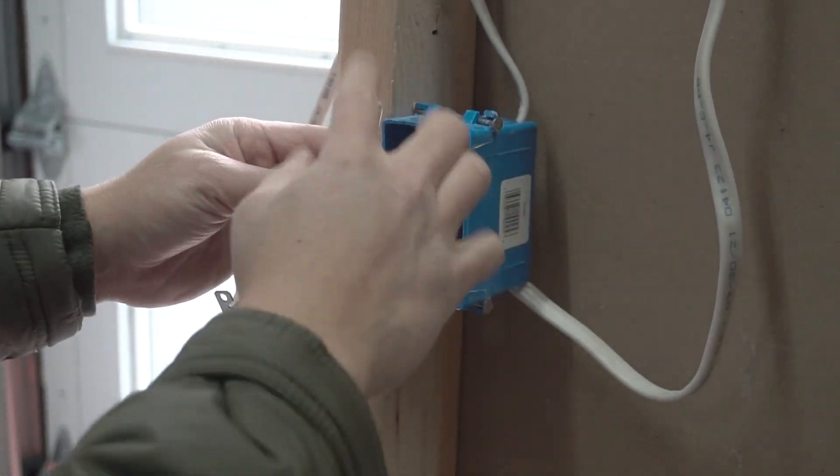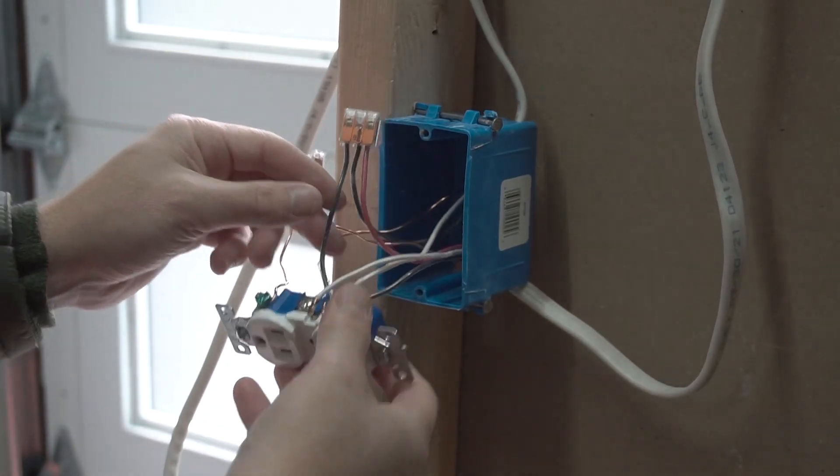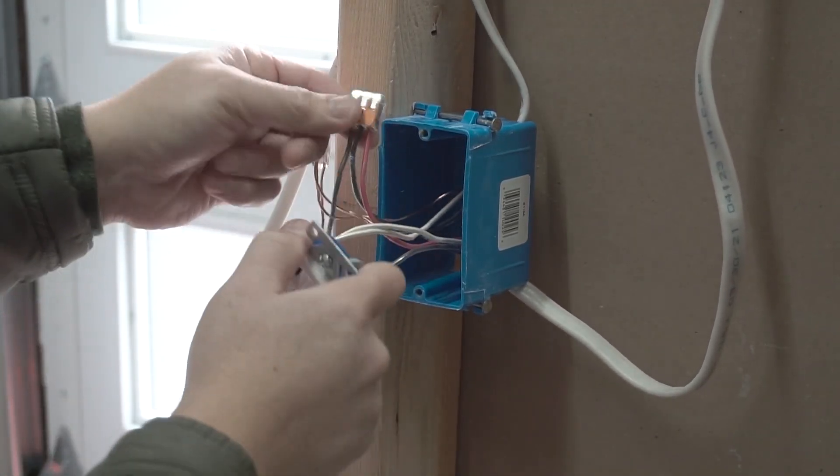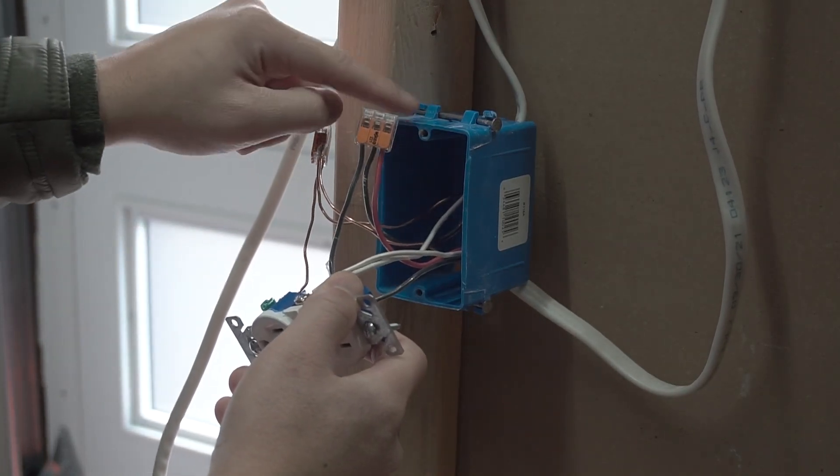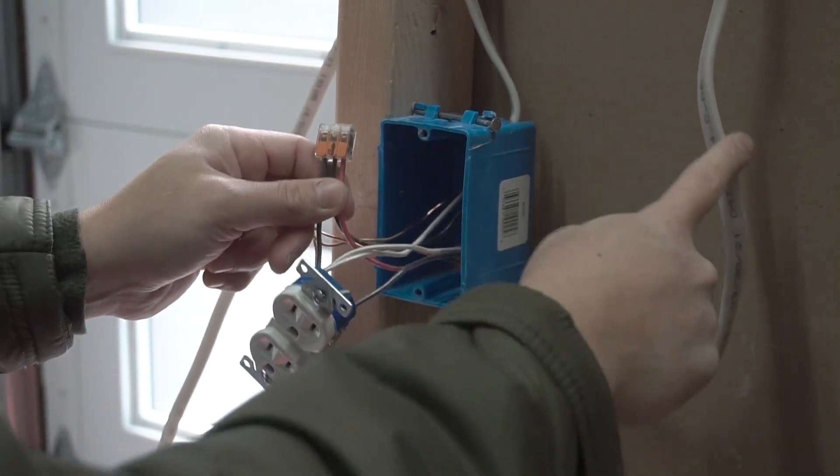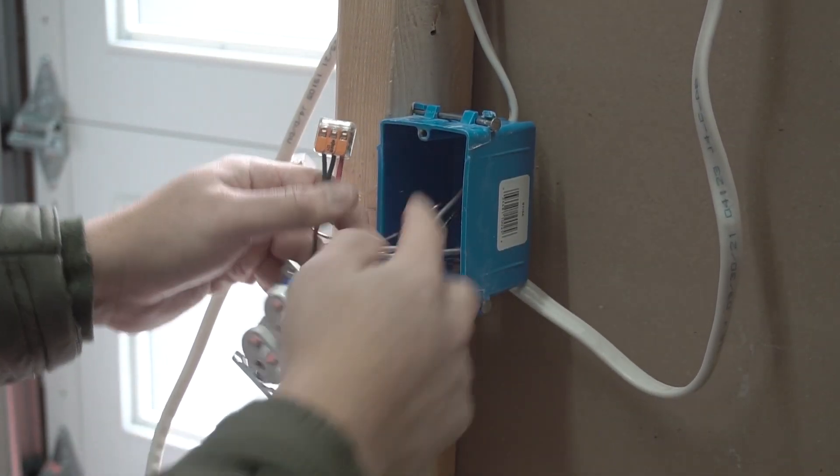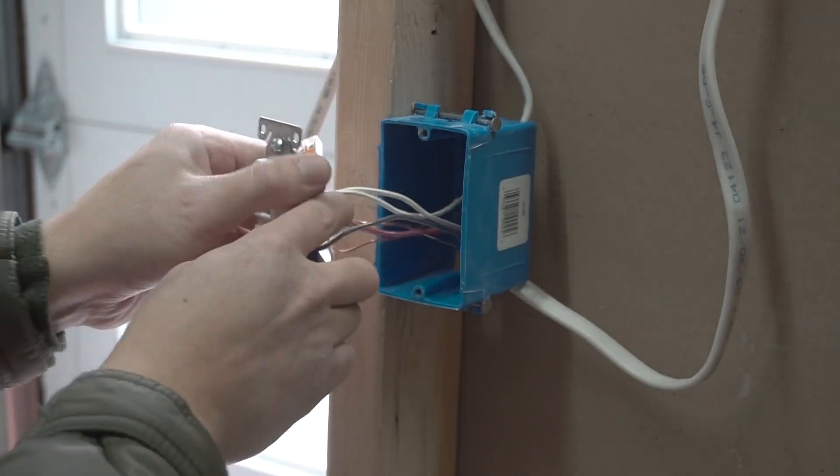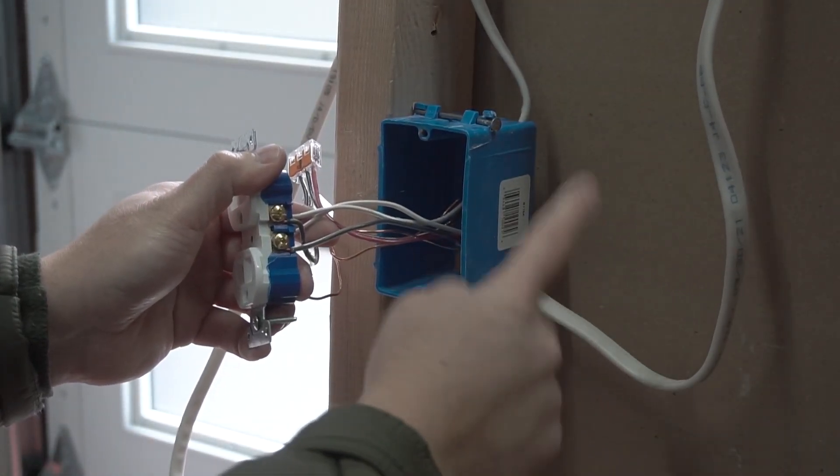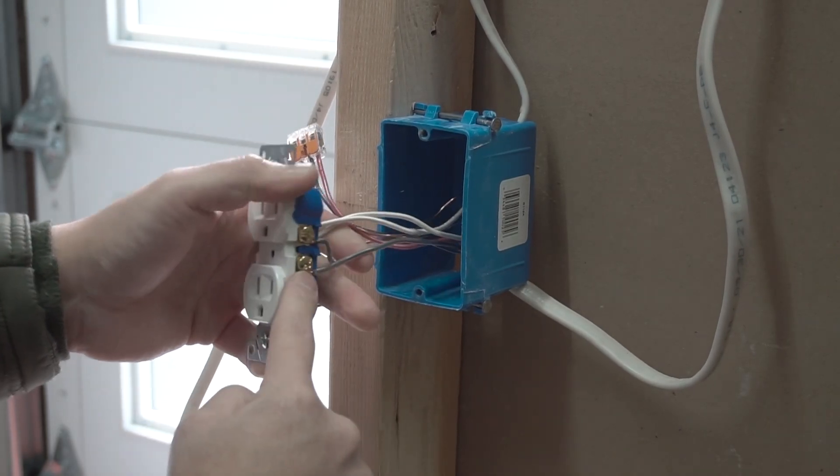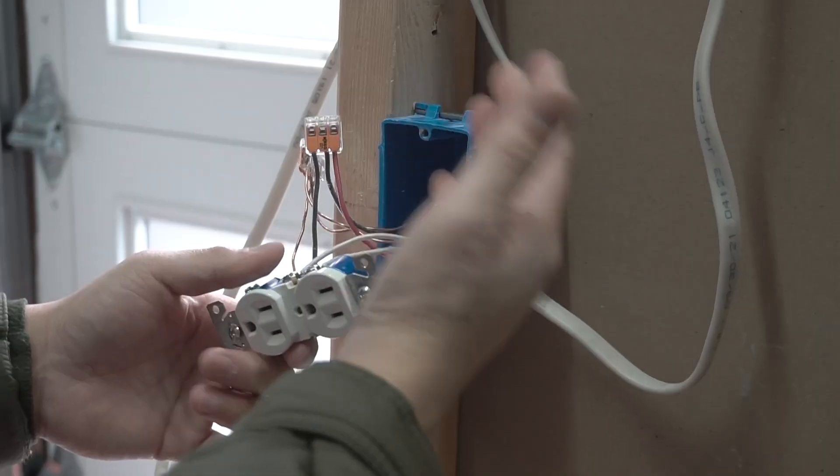Now we have our black hot wiring. The black wire from this outlet that's pigtailed is connected to the black hot wire 14-2 power source, and the red hot from the 14-3 is also connected onto here. And that black hot wire from the 14-3 is connected onto the bottom terminal of this outlet.